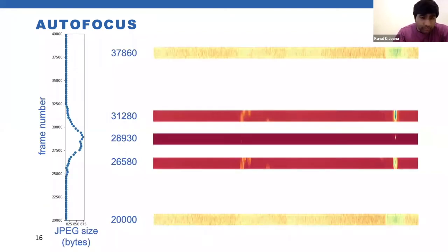So what I mean by finding the focal position is we take an objective stack, where this is sort of a stretched out view of the field of view from just one line. And we continuously image the section as we move the objective away from the section. Then each of these frames we convert into a JPEG. And when you convert it into a JPEG, the larger the file size of the JPEG image, the more in focus the image is.